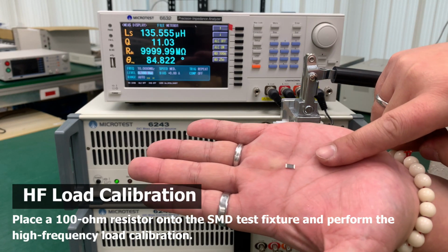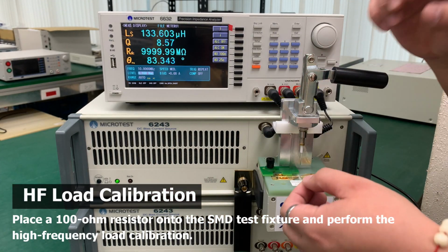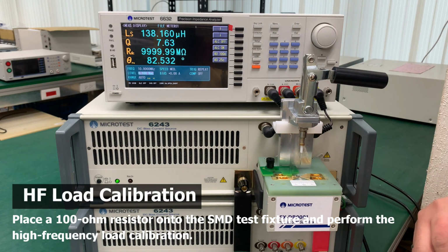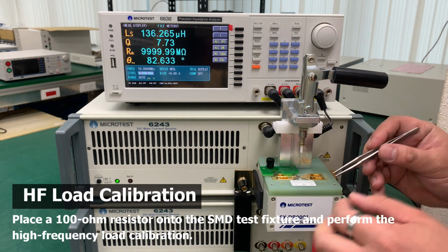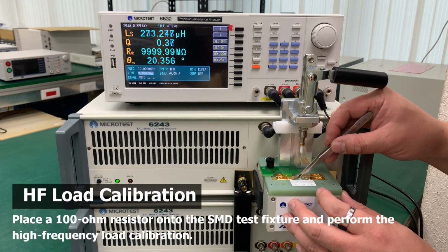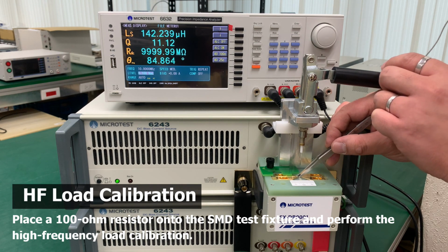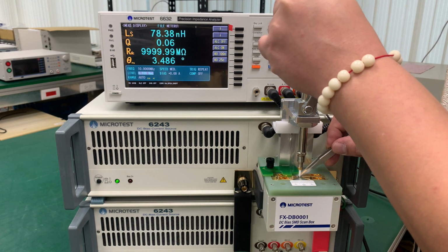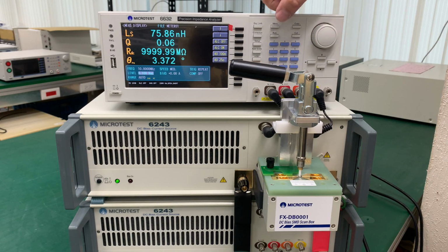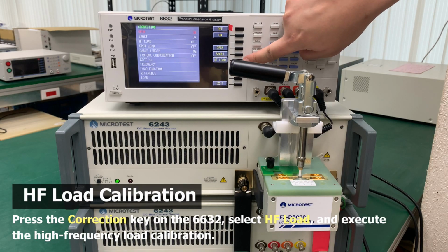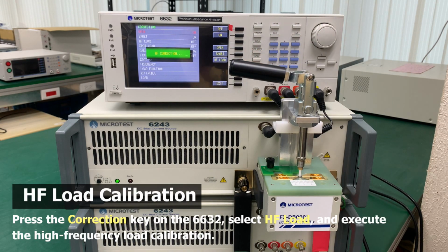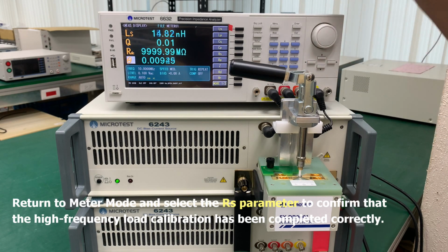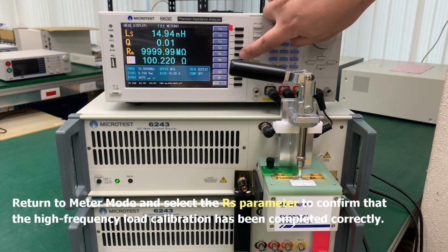Place a 100 ohm resistor onto the SMD test fixture and perform the high-frequency load calibration. Press the correction key on the 6632, select HF load, and execute the high-frequency load calibration. Return to meter mode and select the Rs parameter to confirm that the high-frequency load calibration has been completed correctly.